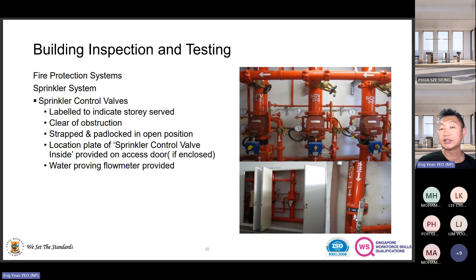All right, sprinkler tank. Yep, this one, for example, the capacity needs to be indicated, right, the water level. Okay, I mean, this is still okay. You can see there's this water level in those transparent pipes, right? If you can't see it from far, then better throw in a styrofoam ball that you can buy from Popular or any stationery shop. Actually, put in a ping pong ball and throw it. At least you can find it and see whether the water level is what we expected. All right, because all this water coming in is through PUB. It's a constant flow of water, and it's being controlled by the ball float valve. All right, for example, this is my ball float.